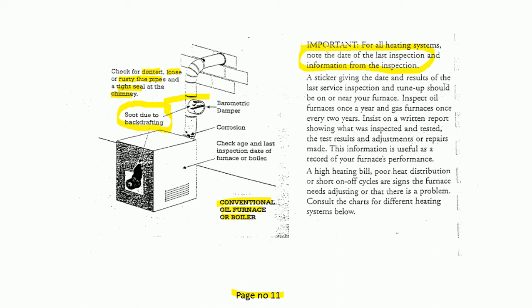And I know for this two-bedroom house, let us say for the whole year, they have to pay in this area $2,000 for the gas bills. And this house, they paid $3,200. Oh, this is 60% more than the average. Yes, maybe they have more equipment, maybe they are home more often, but this has to be 10-15% more, not 60%. So most likely there is a real problem with the system itself, with the system efficiency, or most likely, I would say, it's with the building envelope. There will be more heat exchange, more loss of heat, and this means more consumption of gas. And as a final result, more cost for those bills.